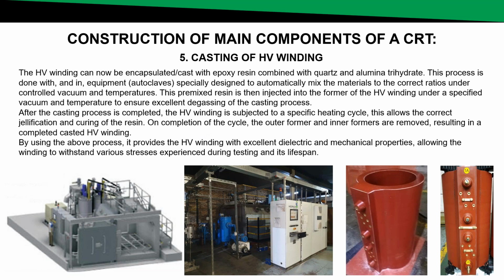This allows the correct jellification and curing of the resin. So should you also not follow the prescribed heating cycle, you will also find that the resin will either cure too quickly or too slowly, also compromising the insulation and later the PD testing of that high voltage winding. Once the heating cycle has been completed, the outer and inner formers or jackets can now be removed, resulting in a complete casted HV winding.